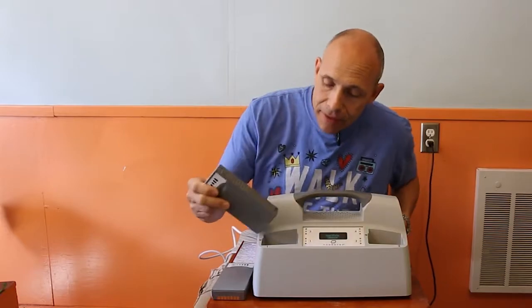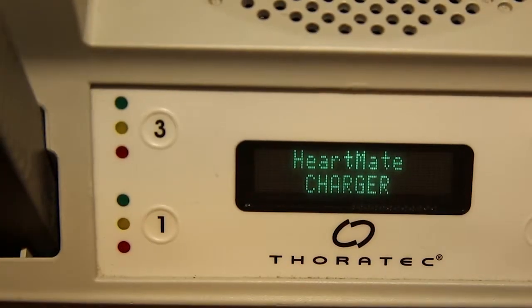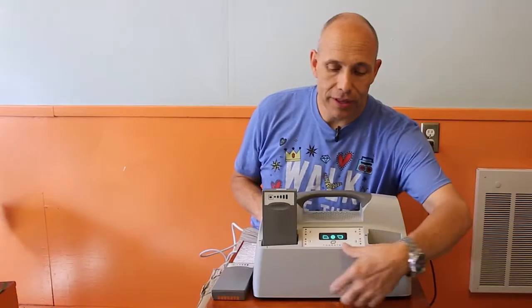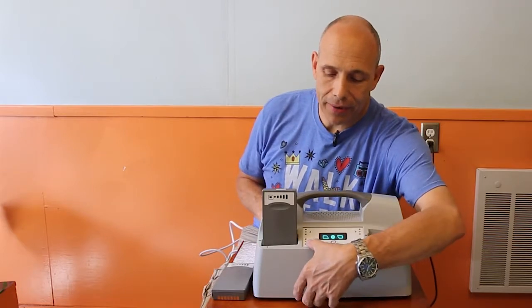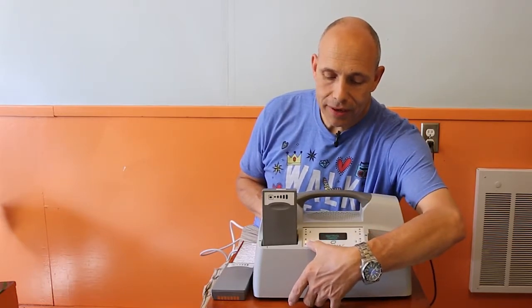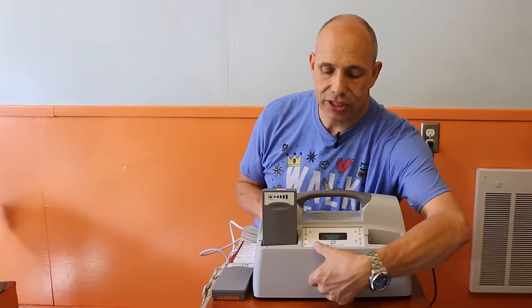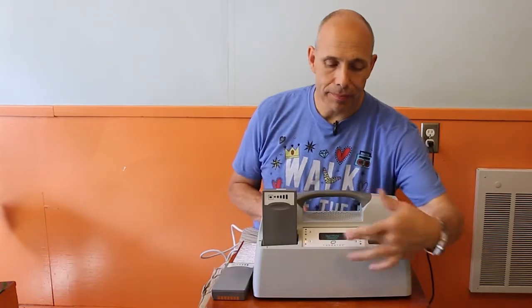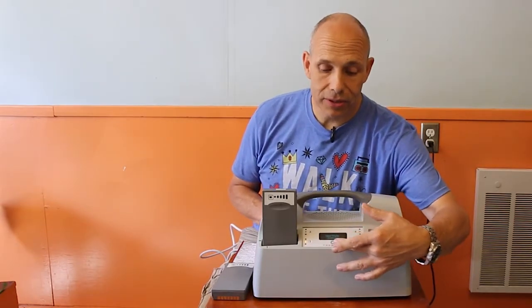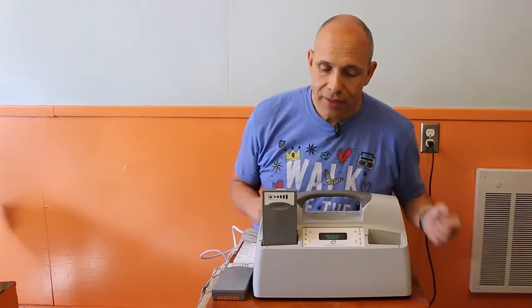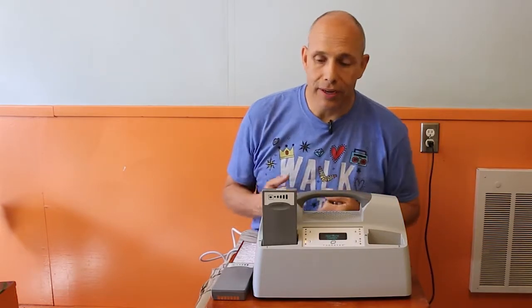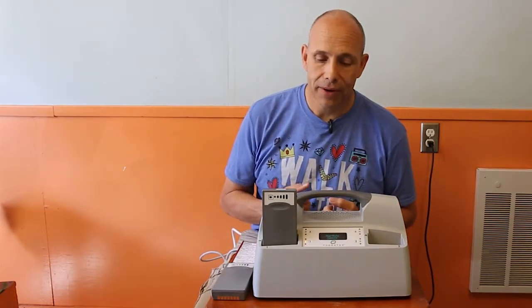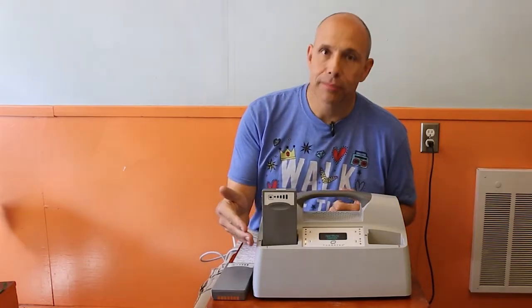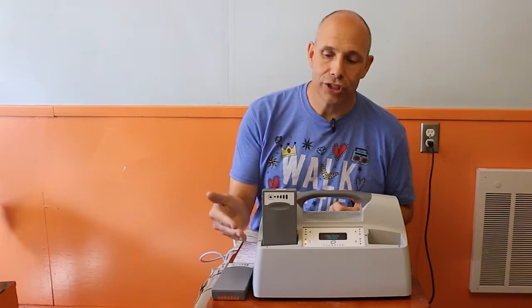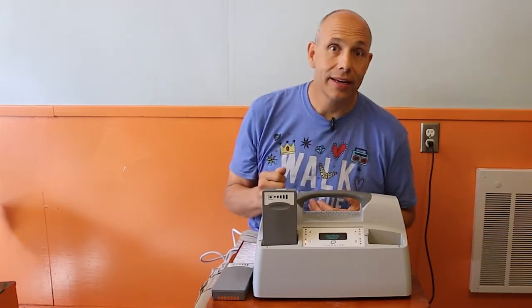Dirt simple. Basically, all you need to do is drop the battery in, and within the first 10 seconds after you drop the battery in, press the number button corresponding to the battery. I just pressed the 1 button. It appears the display goes back to normal, just displays Heartmate charger, and it has now begun calibration of this battery. Over the next 12 hours or less, it will run this battery flat and then fully recharge it, and that indication will go away.